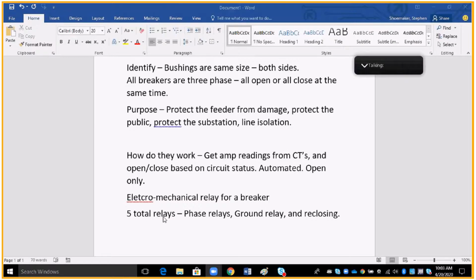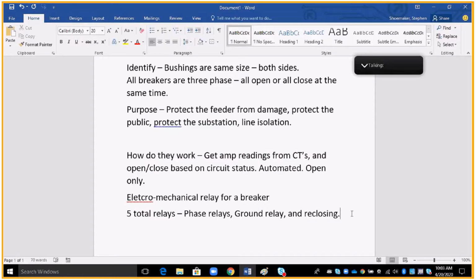All right. 5 total relays: phase relay, ground relay, and reclosing. Let's talk about their individual purpose. Phase relays detect the fault on each phase. If I have an A relay, it's only detecting a fault on A. If I have a B relay, only on B. And if I have a C relay, only on C. Remember though, all breakers are 3-phase, all open or all closed at the same time.